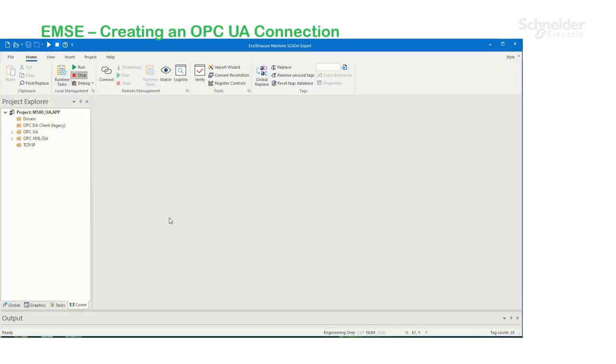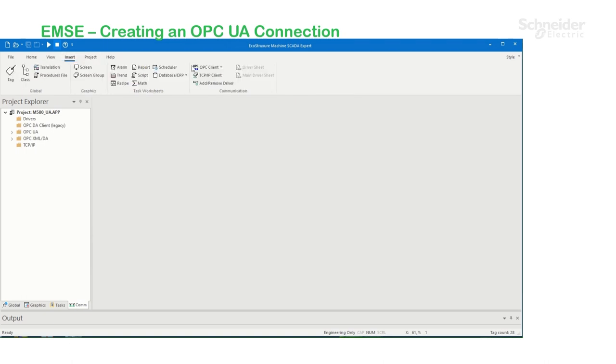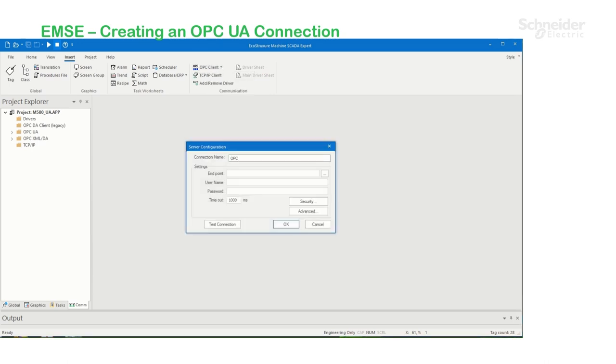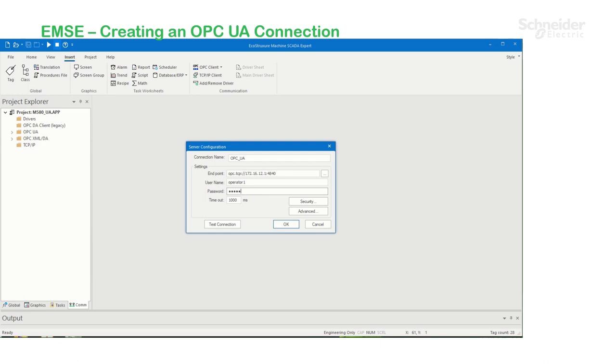Now, in Machine SCADA Expert, I'm going to create an OPC UA connection. Under the Communication tab, click on Insert, and under OPC Client, select OPC UA connection. Here, I'm going to give it a name. Here's the endpoint URL of the BME NUA module. And here's the credential of the user I created under Access Control. I'm going to increase the timeout.